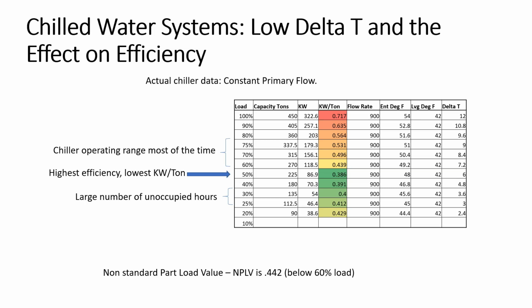So another question, I guess it's related, and again, I may be mistaken, but I thought a sweet spot in general for chillers was 10 degrees. You were looking for a delta T of 10 degrees. Right. And so if we had a delta T that was below 7 or so, we would start thinking, well, maybe it could be more efficient. Yeah, in this case, if it was 7 degrees, the most efficient point is 6 degrees. Right. And so that kind of goes against that. If I could maintain a 10 degree delta T with a better efficiency, I'm going for that. In this case, they're looking at 12 degrees at the maximum capacity. We never reach that. And this building never gets that load. And so this is kind of overkill. So we may not have the best option, and this really cries out for variable flow.